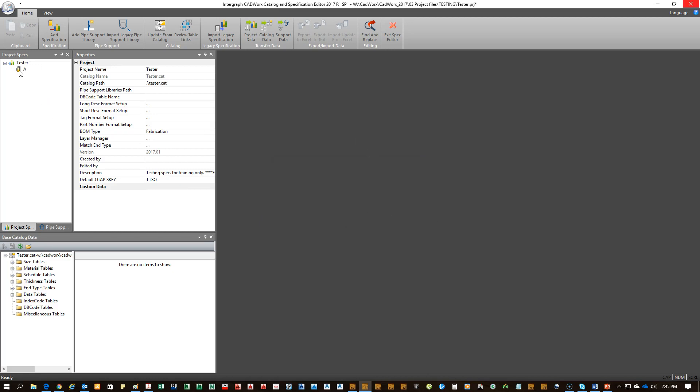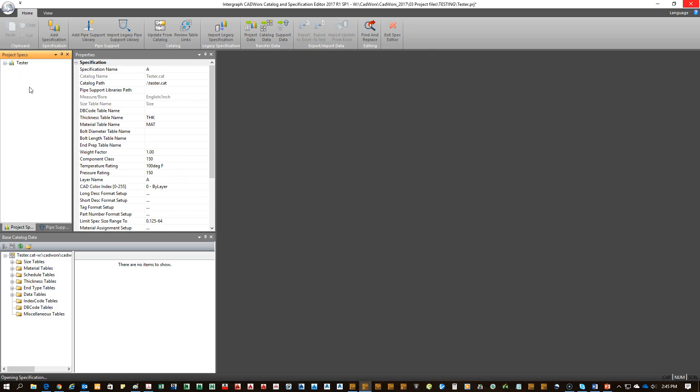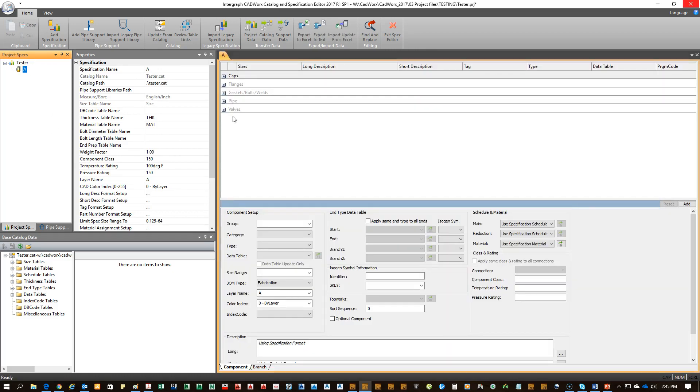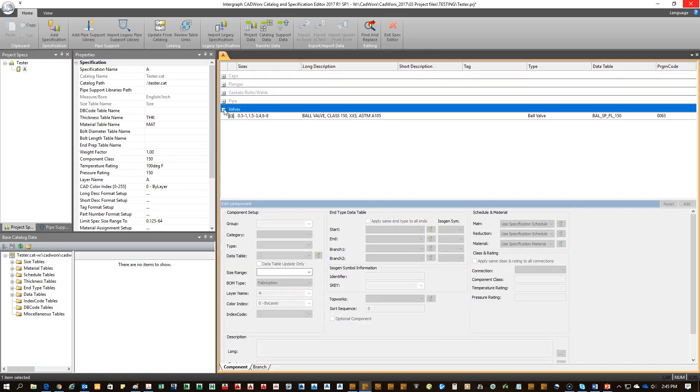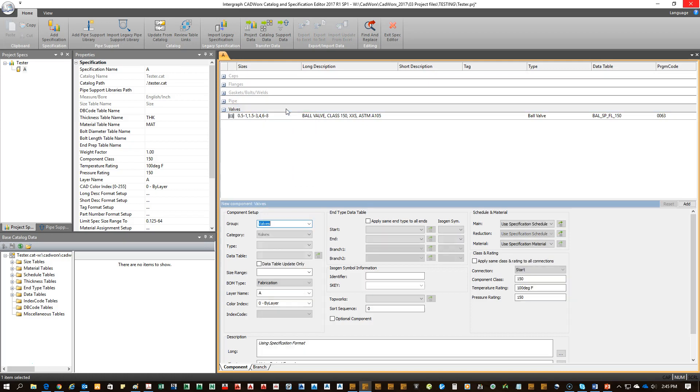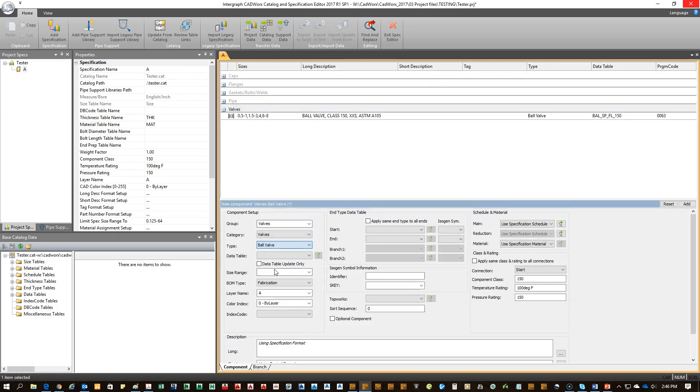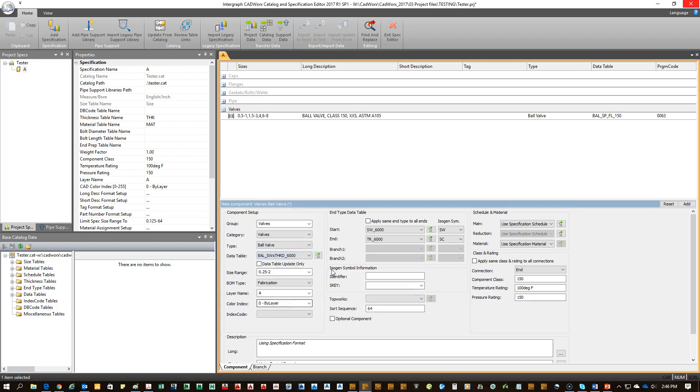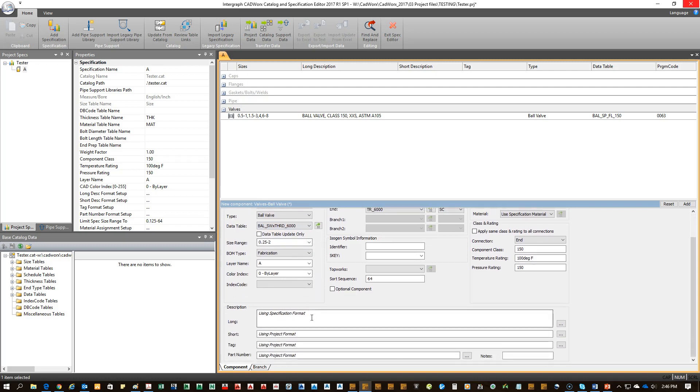Okay, with those both done, I can double click my spec. Come into valves. I click add. I'll pick the type, ball valve, pick the data table I just built. It's a 6,000 pound. It automatically brings in the sizes that are available for that data table. And then I can build my long description.